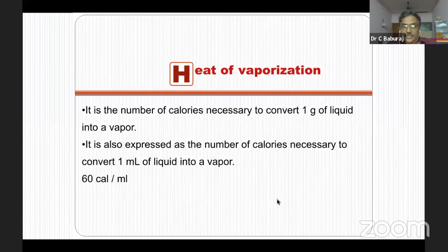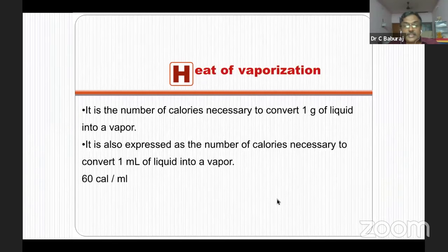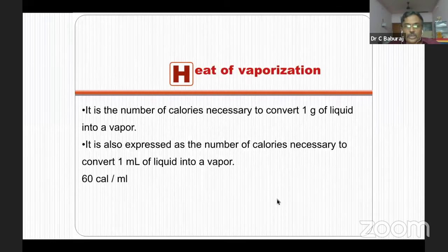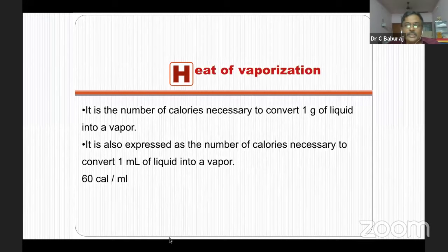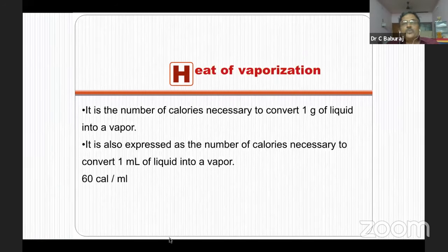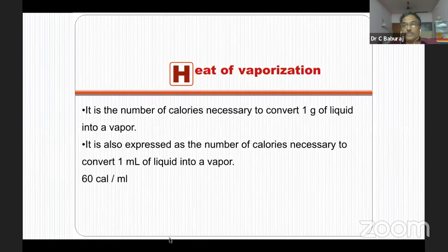Heat of vaporization is the number of calories required to convert one gram of liquid into vapor. Generally for all anesthetics, around 60 calories are needed to convert one ml of anesthetic into vapor. When the liquid becomes vapor, it cools down. Because of the cooling, kinetic energy in the body of the liquid comes down and vaporization is slowed. So in a vaporizer, if you take no measures to keep the temperature stable, vaporization gradually comes down and vaporizer output concentration gradually falls. You have to provide this heat of vaporization to maintain stable temperature and constant vaporization.